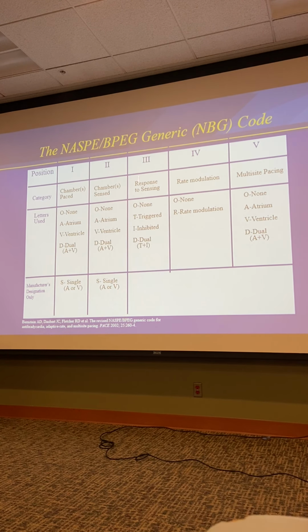That non-programmable rate changes based on the condition of the battery. So that's, without using a programmer, one of the ways that we can do a quick and easy test to see if someone's battery is running down. When it gets down to about 80%, it hasn't stopped working yet, the rate at which the pacemaker paces when a magnet's applied changes to an alert rate, a rate that you can look up from the manufacturer, and it says this is a low battery state. And then there's this pacemaker-mediated tachycardia, which we'll talk about. Magnets are the quick and easy way to stop a pacemaker-mediated tachycardia. You just apply the magnet, count to 3, take it off, and the tachycardia will be gone. And we'll talk about that in a moment.